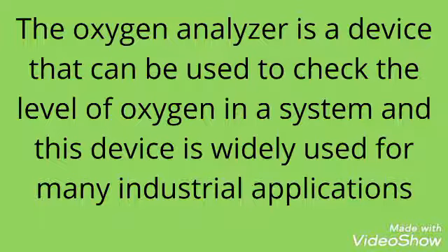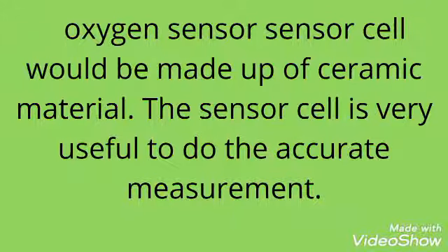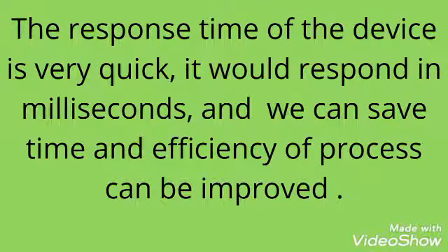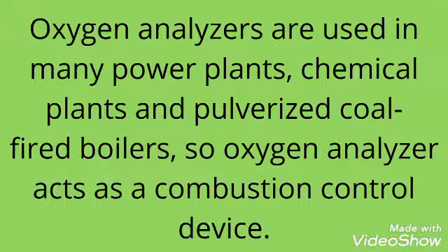An oxygen analyzer is a device used to measure the oxygen concentration in a system. It is mostly used in industry. The sensor should be made of ceramic material. This sensor is very useful for accurate measurement of oxygen concentration. Response time is very quick, in the millisecond range, so we can save time and increase efficiency.